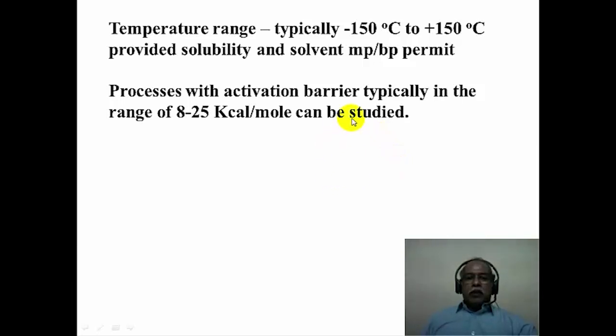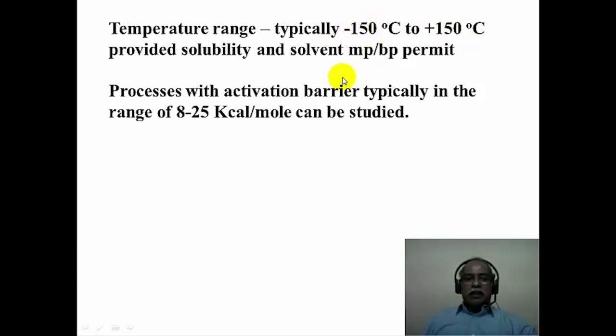The sample tube in the NMR spectrometer can be cooled to minus 150 degrees Celsius or heated to plus 150 degrees Celsius. This 300-degree window is accessible provided the solubility and the solvent melting point and boiling point permits such an operation. It is possible to study processes with activation barriers typically in the range of about 8 to 25 kilocalories per mole using NMR spectroscopy.